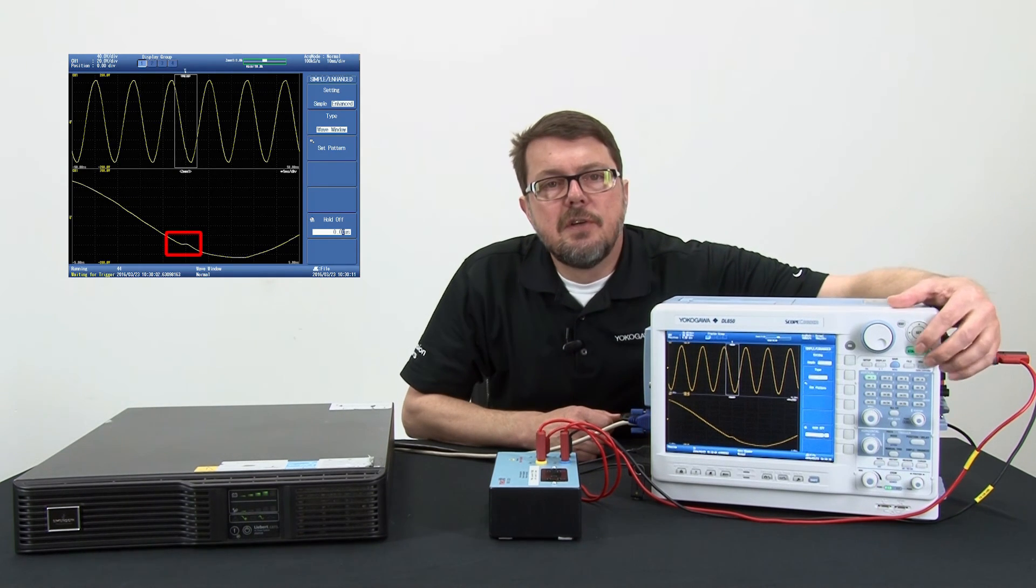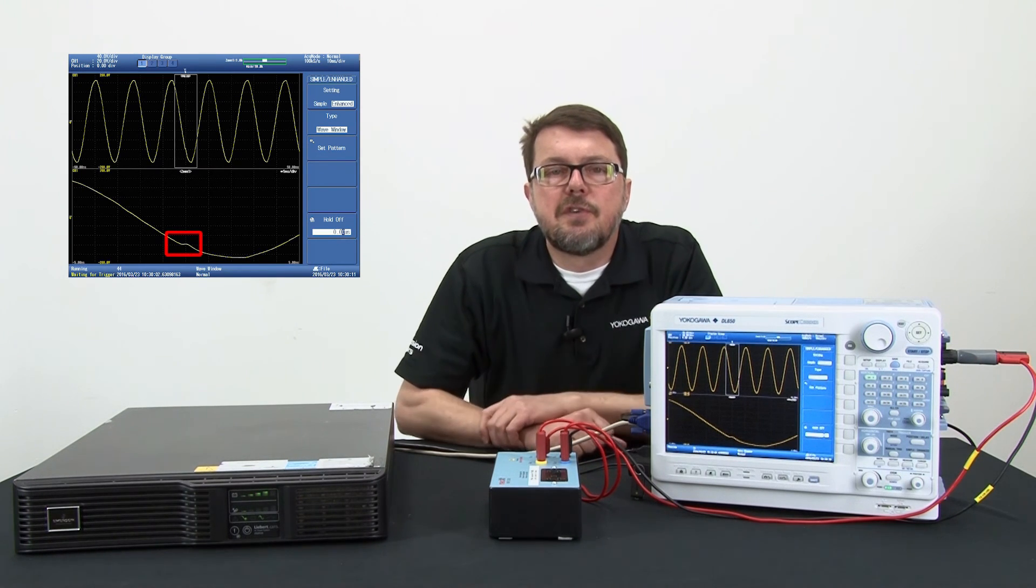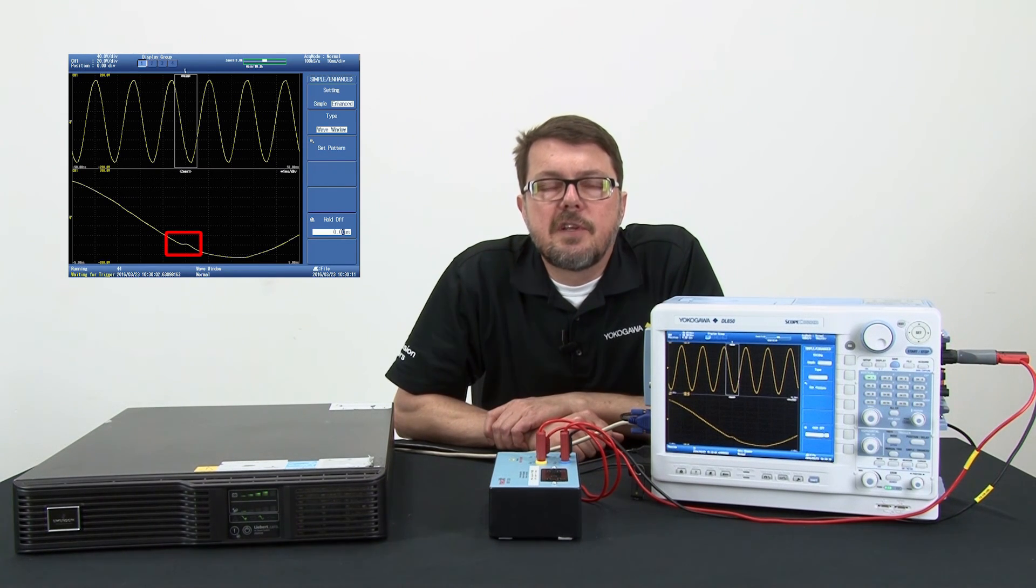We've captured our glitch. I'm going to press stop, and we can use the zoom feature to zoom in on the glitch during the UPS switchover.